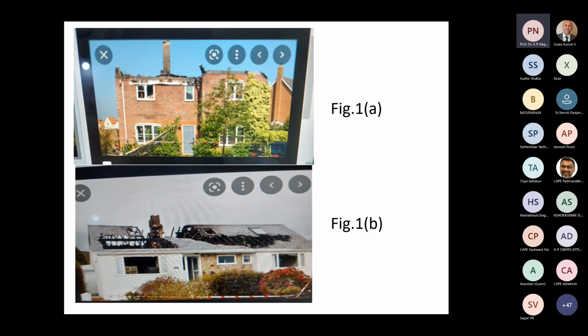Figure 1A shows that a whole parapet of a building has got shattered because of the lightning incident. Now the next one, 1B, shows the extensive damage that can occur to the top of a building if it's not properly protected. It's very, very extensive. Almost the whole roof has disappeared because of this. Of course, the type of damage that would have occurred inside, one can really imagine by looking at the damage that is seen in the photograph. Really, it can be very bad.